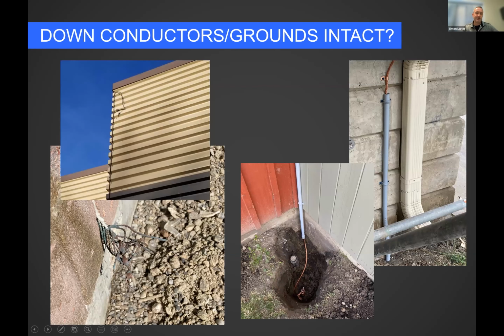Are they intact? For the most part you should be able to tell - if it's exposed, you can do a visual verification that the down conductors and grounding are intact. Although on the left-hand side at the top, yet again, it's another roofer special - they did a re-roof on a very upscale school in the Calgary region and just left that down conductor hanging, never putting it back on. When we went to inspect, we noted they'd made the building significantly less safe. The roofer actually called me afterward and asked for a quote to put it back on.